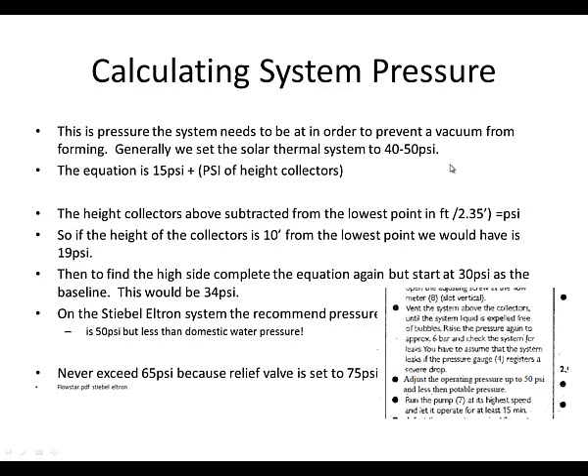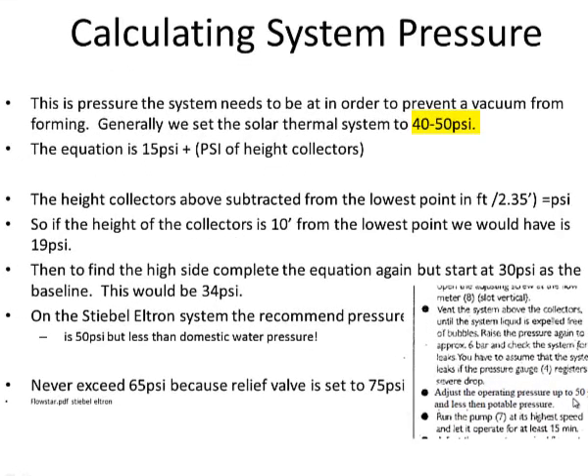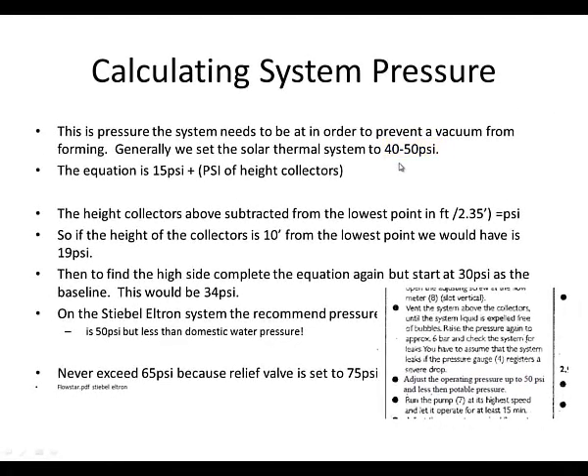To calculate the system pressure, the first thing we want to do is check the manufacturer's specs. According to the Stiebel Eltron Flowstar data sheet for the installation, they recommend raising the system pressure to 50 PSI — a range of 40 to 50 PSI. On your closed loop system there will be a pressure relief valve, which is typically set to 70–75 PSI to prevent overpressure situations.